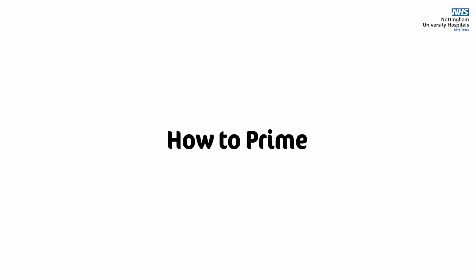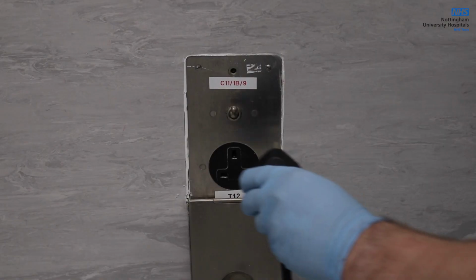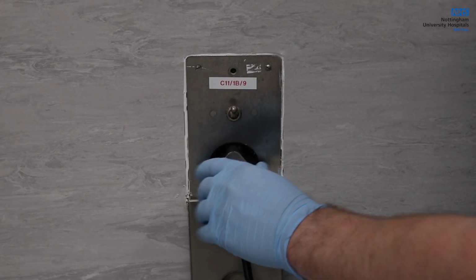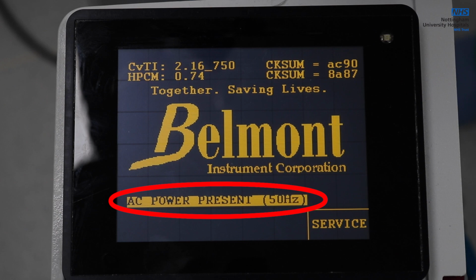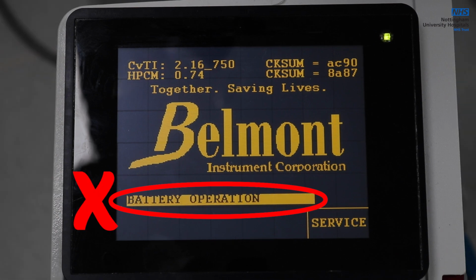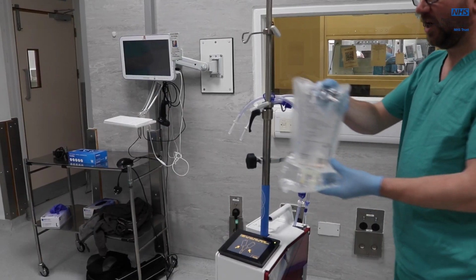How to prime the rapid infuser once disposable set is installed. The device must be plugged into the mains power point and not a power extension or set lead. You must ensure that mains power present is shown on the startup screen, not on its internal battery.